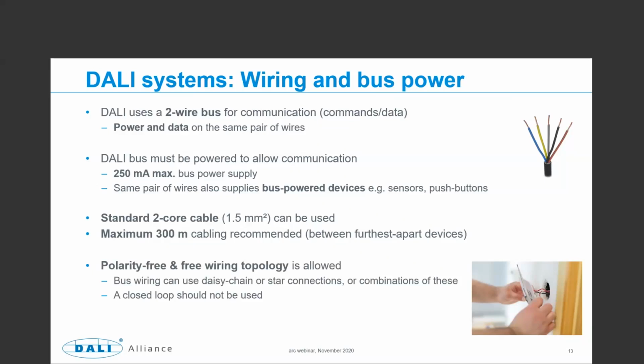And DALI is polarity free, and it's a free wiring topology. So you can connect the wires either way around, except for the bus power supplies, of course. If you have more than one of those, they need to be consistent. And also a free topology. So you can daisy chain, or you can use star connections, or even a combination of those. We don't recommend closing the loop. That can cause other problems.